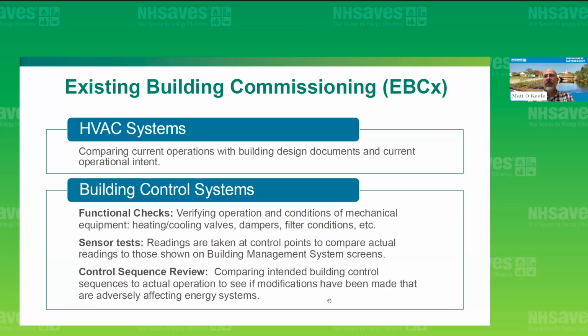That we're finding a site that, especially if they've got some form of a building management system, and we're going to focus on the commissioning of, for this purpose, we'll call it HVAC systems, where there's a good way to establish a positive relationship with a customer. Typically, you're going to be finding things that will save energy and increase comfort. So that's usually a good way to leave a customer, that you're able to do that for them. And the main areas and steps that are reviewed by commissioning agents: they're doing functional checks of mechanical systems, sensor testing and comparison of what the building management system might be showing versus what the condition really is out in the field, and then sequence review.